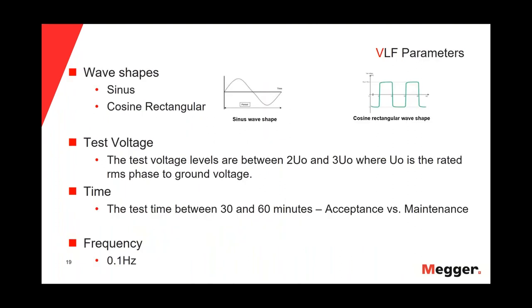The most important parameters in the VLF test are the wave shapes. The two most common wave shapes used are the sinusoidal wave shape and the cosine rectangular wave shape. Both have their own advantages and disadvantages. The sinusoidal wave shape units are lighter, smaller, and cheaper. Also, we can use the sine wave shape to do the tan delta test. The disadvantage of the sine wave shape is that at 0.1 Hz we have a limited test capacitance. The cosine rectangular wave shape units are heavier and more expensive, but the test capacitance at 0.1 Hz is larger.